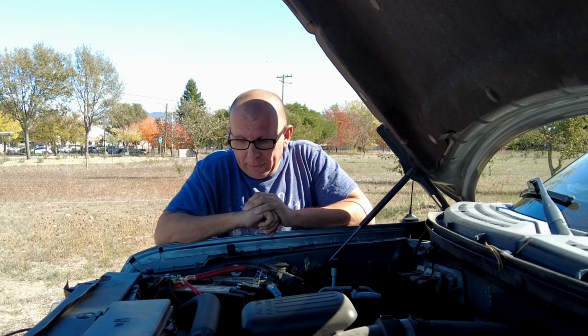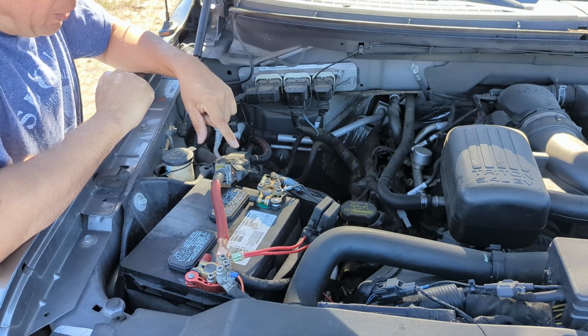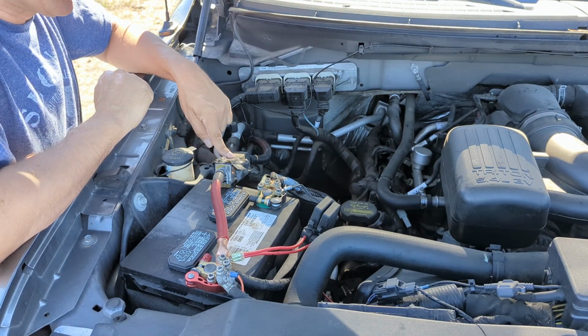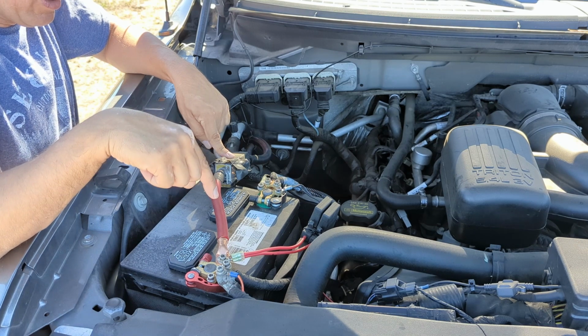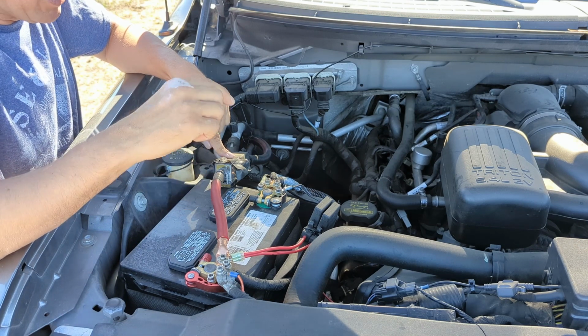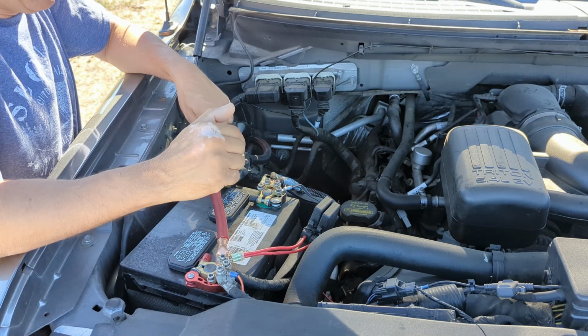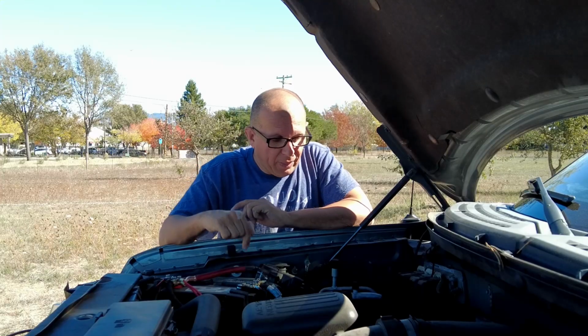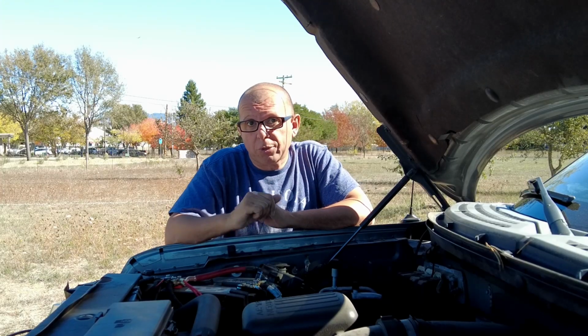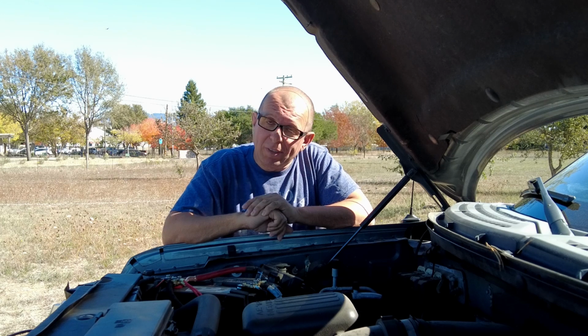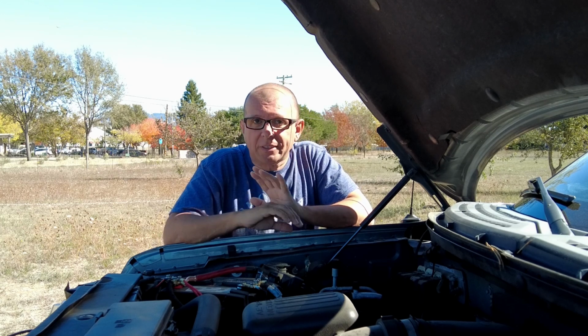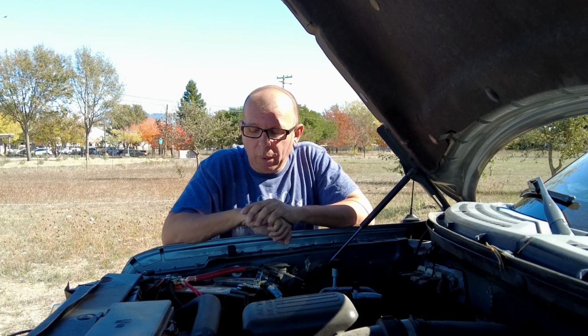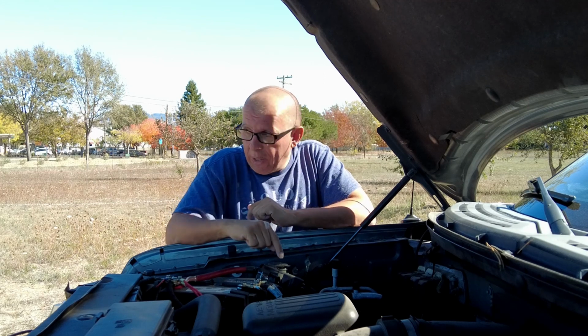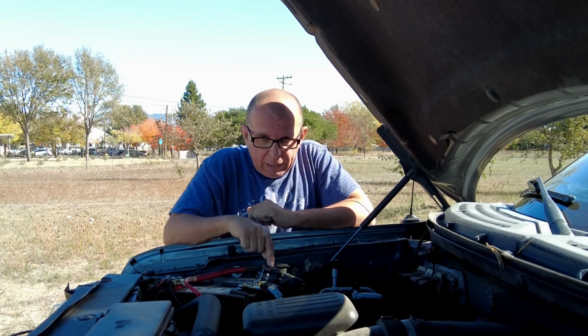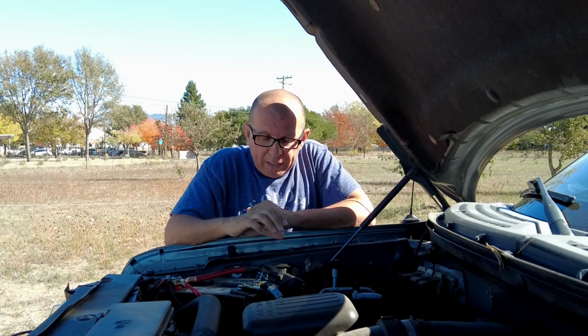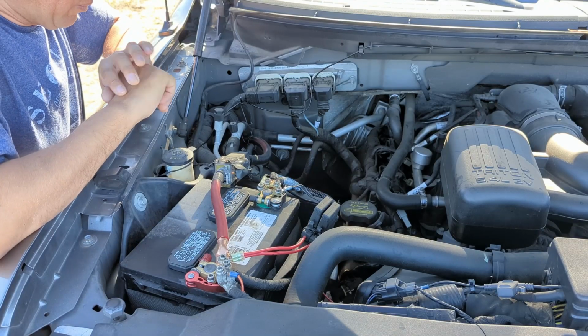I'll explain why. You always want a fuse close to the current source, because if you have an overcurrent situation without a fuse there, the whole wire becomes the fuse and the cable will melt, causing all kinds of problems. So you want a fuse at the beginning to protect the overall circuit.